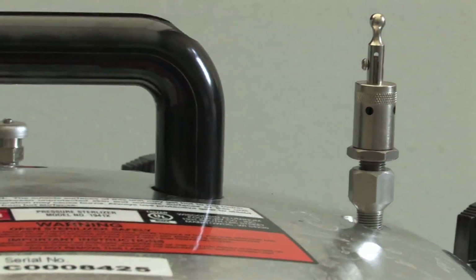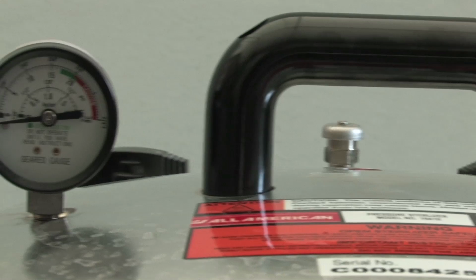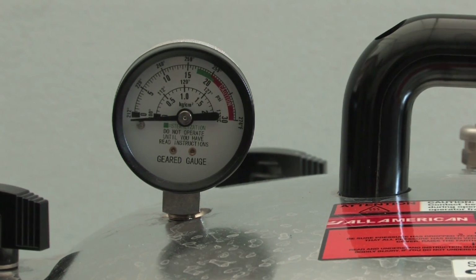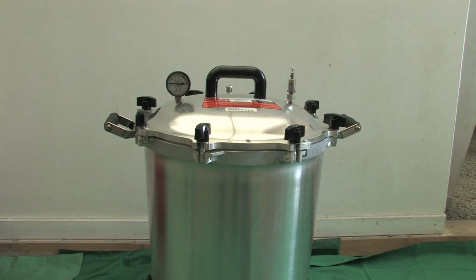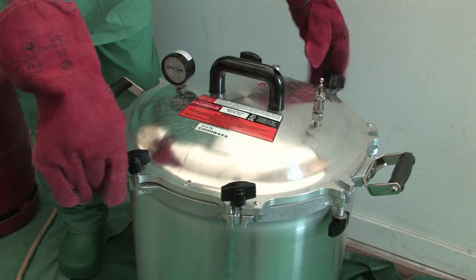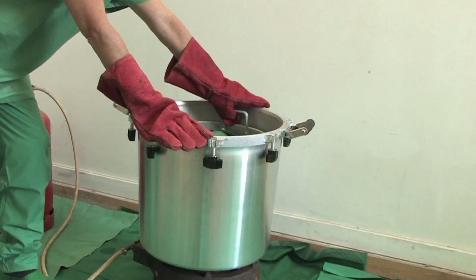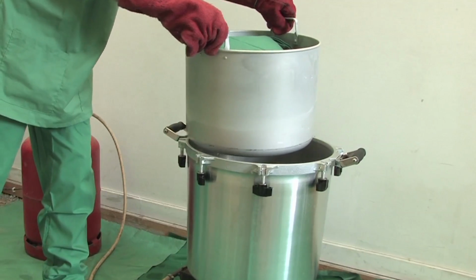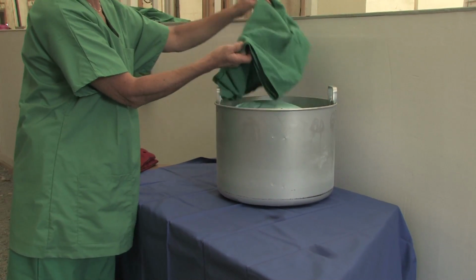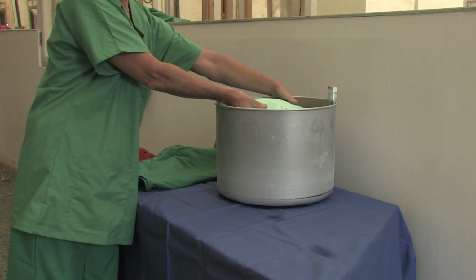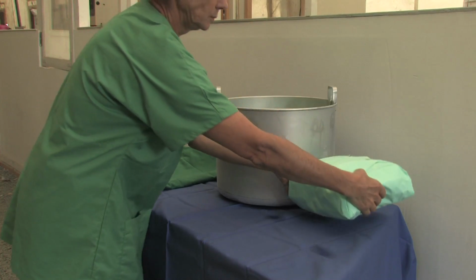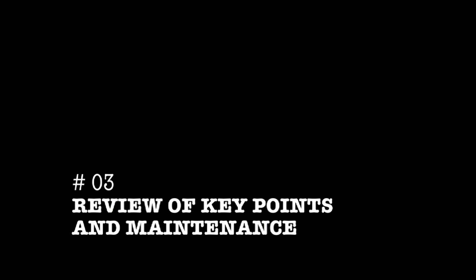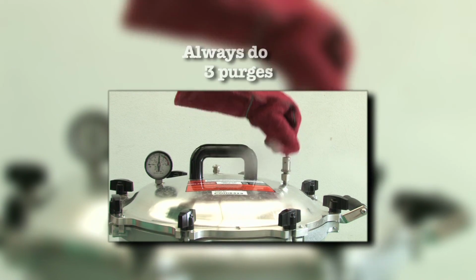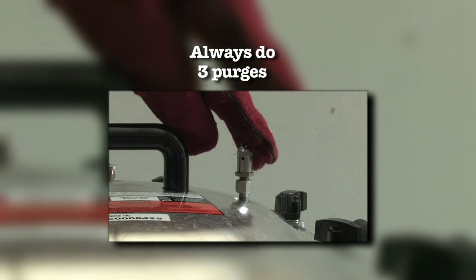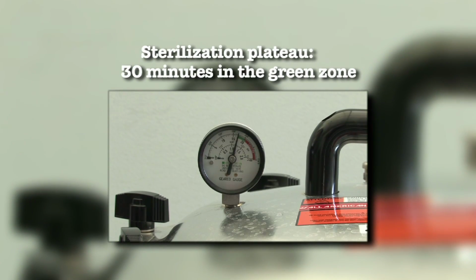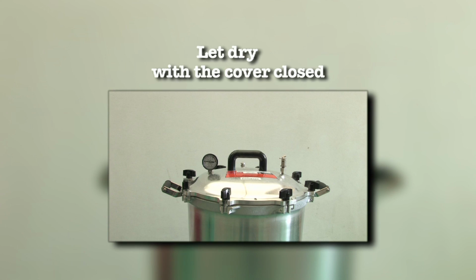12. Open the valve to return to atmospheric pressure or 0 bars on the pressure gauge. 13. When the pressure is 0, unscrew the wing nuts and open the autoclave. Remove the crepe sterilization paper or cloth covering the equipment. Remove the packs. Always do 3 purges. Sterilization plateau, 30 minutes in the green zone. Let dry with the cover closed.